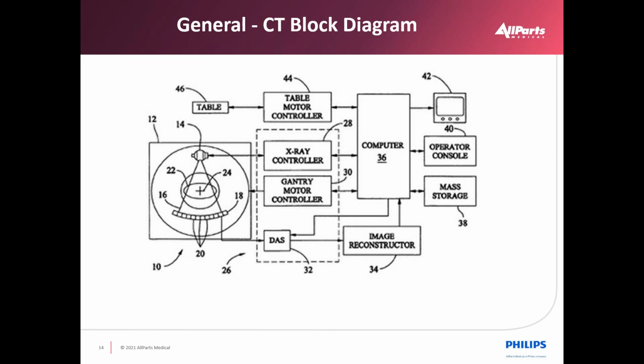The X-ray tube and the detector both rotate around the patient. In a 4th generation scanner, only the X-ray tube rotates around, and on a fixed circle there would be detectors all the way around. That's very cost prohibitive when we get into multiple rows, where instead of just having one row like we did with early CTs, we have up to 64, 128, 256 rows now. The more detector elements you have out there, the more expensive it will be to have a 4th generation scanner.